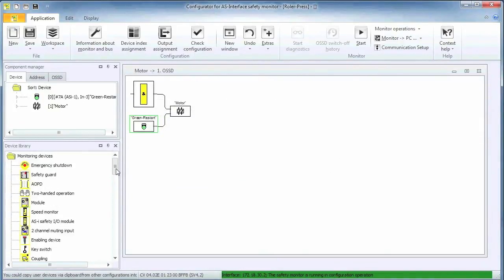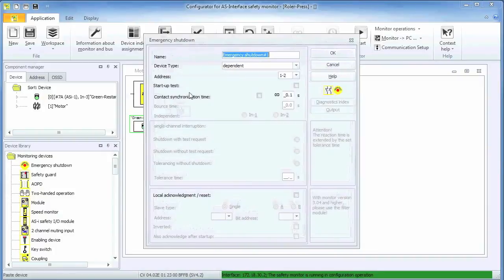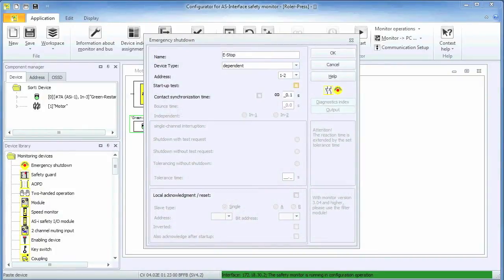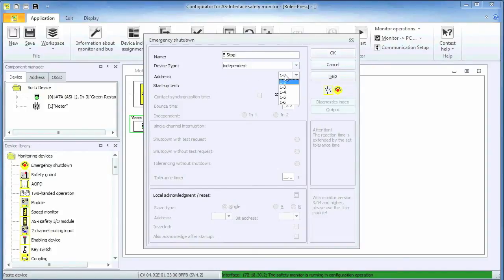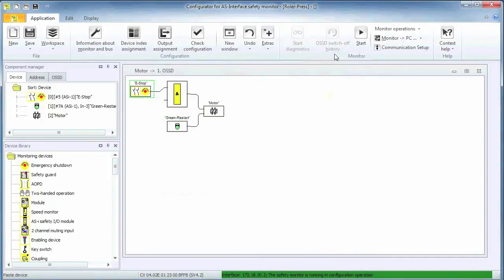Now it is time to add the safety devices. Here is the e-stop on address 5, connected directly to the global AND function. Placing the e-stop function block here assures that it will always be able to remove power from the motor, no matter what else we are going to configure.